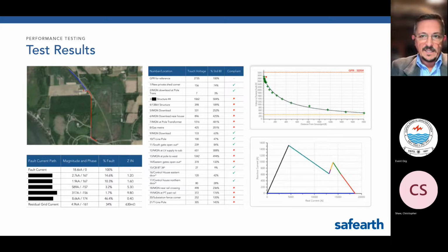Measurement of phase wirelessly is made possible by using a GPS clock signature. So a very accurate clock, setting your source to a particular timing of the clock, and then measuring every other current and voltage compared to that, gives you wireless phase. If you lose the GPS clock, then you're relying on highly stable crystals or some kind of compensation for crystal drift to make sure that you retain good phase accuracy for some time, if, for example, you're in a cable basement or in a tunnel. So, modern, powerful, very illuminating techniques.